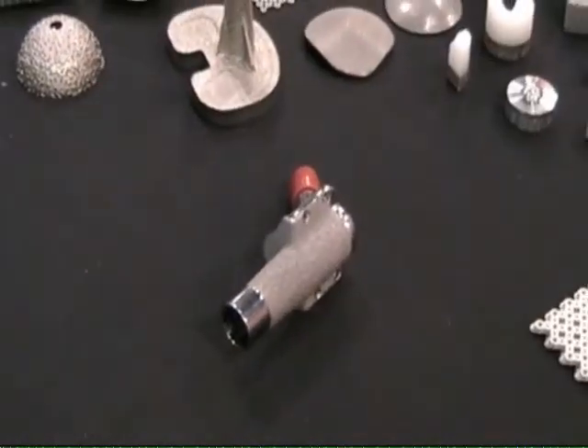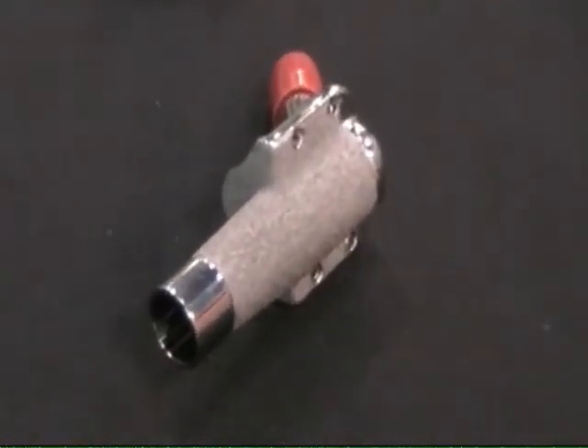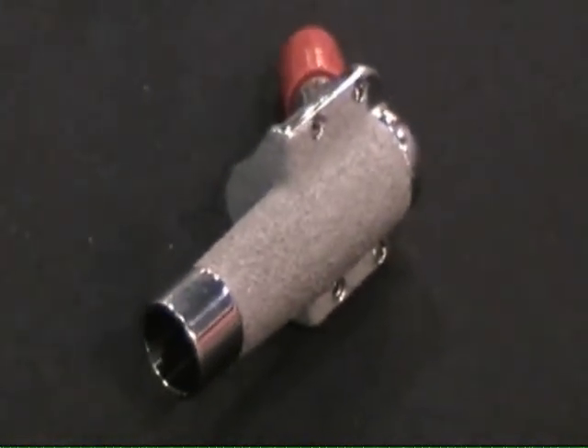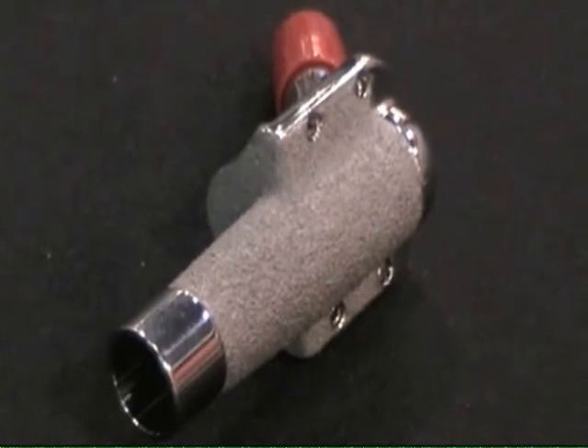Tecomet has developed a novel photochemical etching process that can create surface textures with a subtractive process where chemicals are used to dissolve metal from the substrate material. It can be applied to titanium, cobalt chrome, stainless steel — all the medical implant grade alloys.